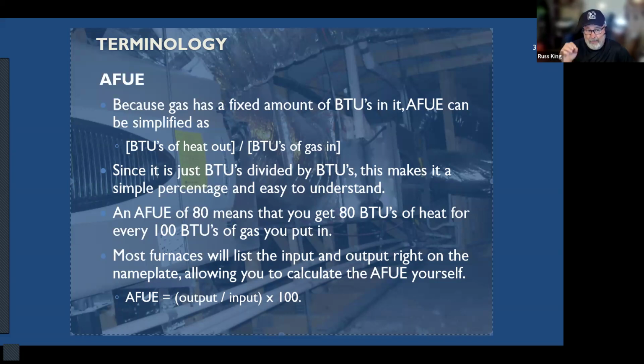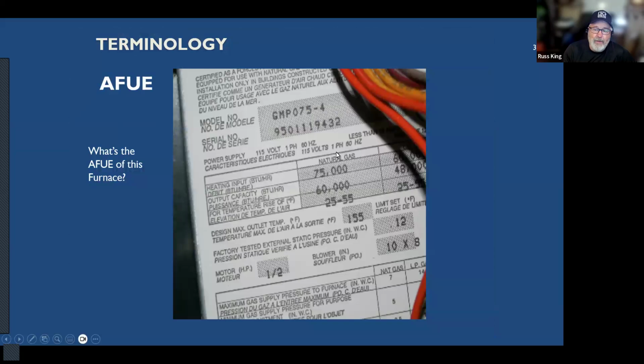Most furnaces will list right on the nameplate the input in gas and the output in BTUs per hour. Okay. And you can calculate the AFUE. So you take the little number, just remember it's a percentage. All right. It's a fraction. So you take the little number and divide it by the big number, and that will give you the AFUE.